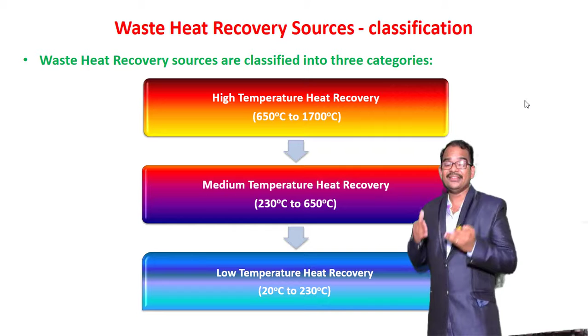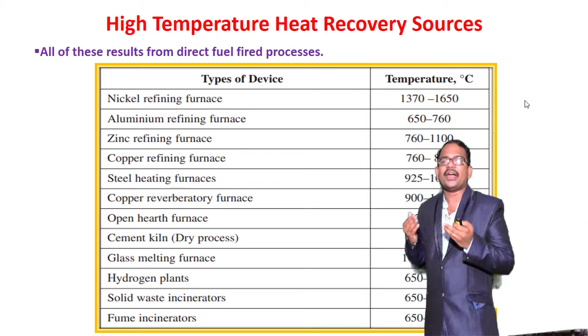Then coming to the high temperature heat recovery sources. What are the different examples or processes from which we get this high temperature heat recovery? For example, you can see in the slides, the nickel refining furnace. The flue gases from the nickel refining furnace will be at a temperature of around 1370 to 1650 degrees centigrade. So we can utilize the heat of those flue gases from that industry's exhaust. Let's take one more example, the copper refining furnace. We get heat at around 760 to 815 degrees centigrade, and we can harness that quality amount of heat from that exhaust stream. Generally, all these high temperature heat recovery sources are obtained from direct fuel fired processes.